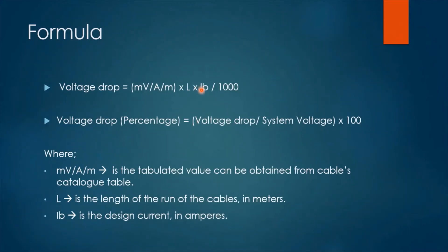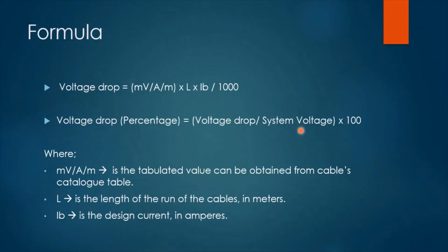Now let's introduce the formula for calculating voltage drop. Voltage drop equals millivolt per ampere per meter (mV/A/m) multiplied by the length, multiplied by the current, divided by 1000. To convert this into a percentage, we divide the obtained voltage drop by the given system voltage and multiply by 100. Here, mV/A/m is the tabulated value obtained from a cables catalog table, L is the length of the cable in meters, and IB indicates the design current in amperes.